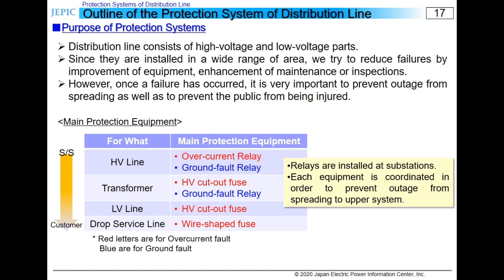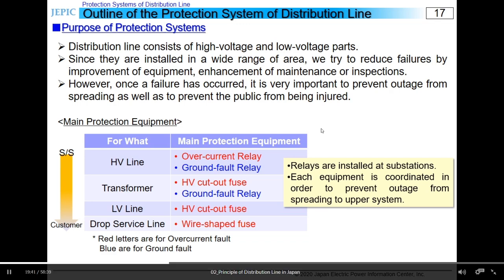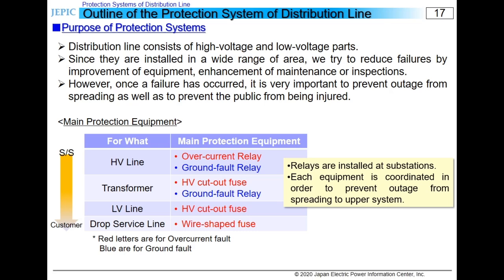The table shows the major protection systems. Blues are for overcurrent. Reds are ground fault. Relays are installed in substation, which protect an entire feeder, and other fuses are protecting its load side and prevent failures from spreading into the upper grid.